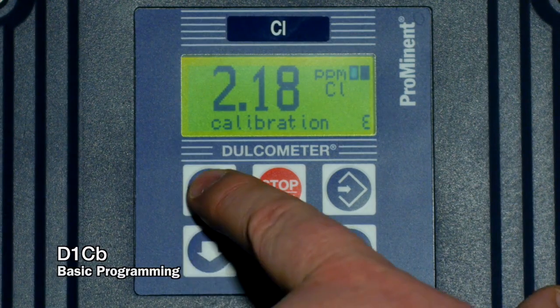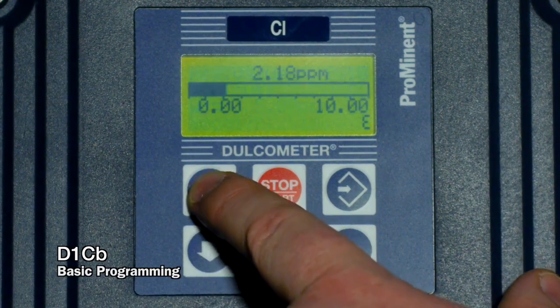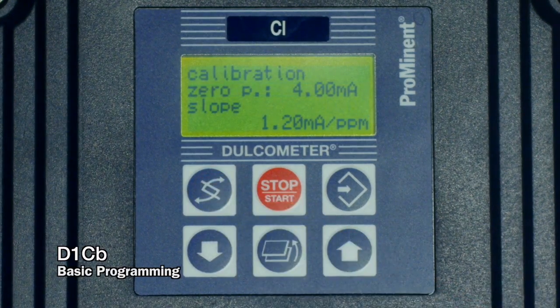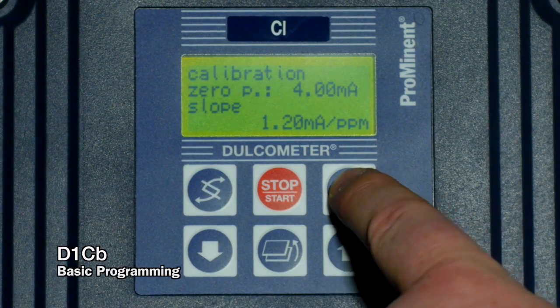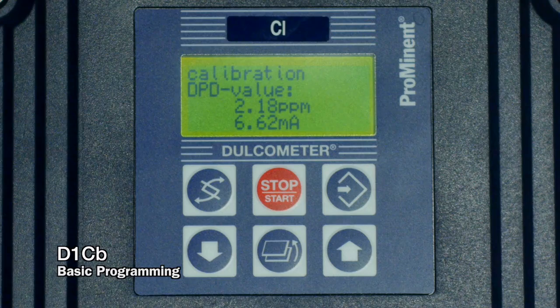From there, to do the calibration, we hit the change key until we see calibration. We hit the enter. It's asking us what that value is. You see that value is flashing, 2.18 in this example. It's very important that we pull our sample at the moment we go into this screen where that value is flashing. That's what the reading is representing.